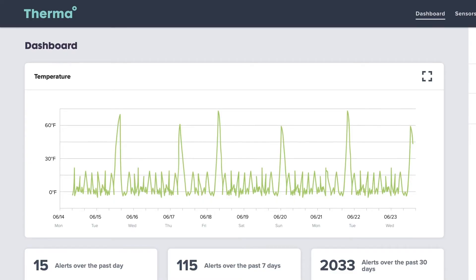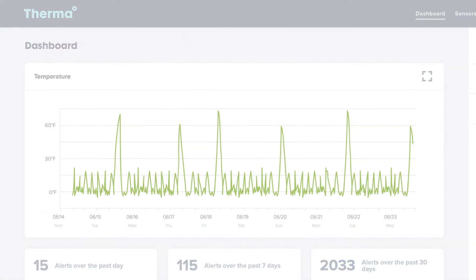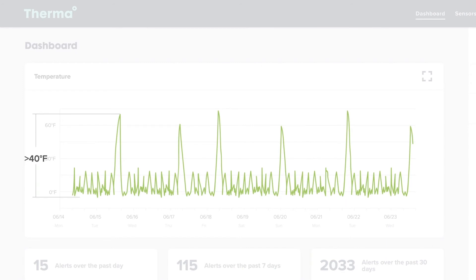As in the previous example, we recommend turning down the temperature of this unit to see if this resolves the increase in temperature. In this instance, you can see that there are multiple substantial variations in temperature for this unit since deployment, sometimes resulting in up to a 40-degree fluctuation in temperature. Suppose this is not the result of a projected or scheduled usage for this unit. In that case, we recommend examining how the equipment is being handled and stocked to extend the lifespan, lessen overall power consumption, and reduce the number of thermal alerts triggered for this unit.